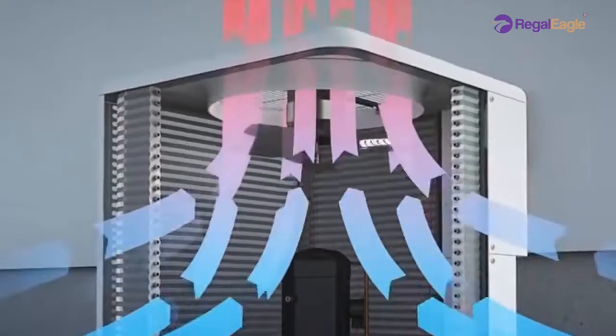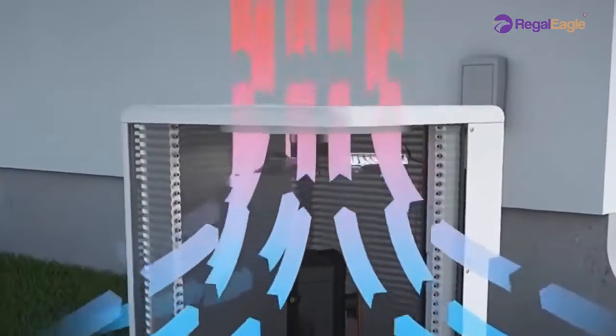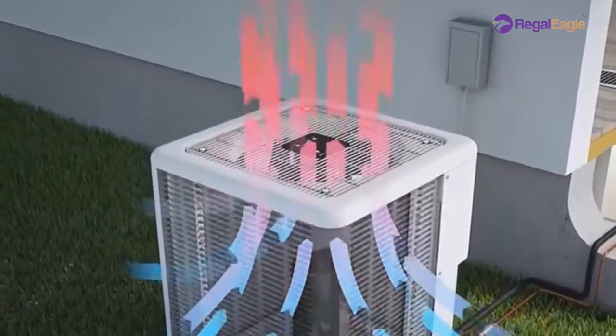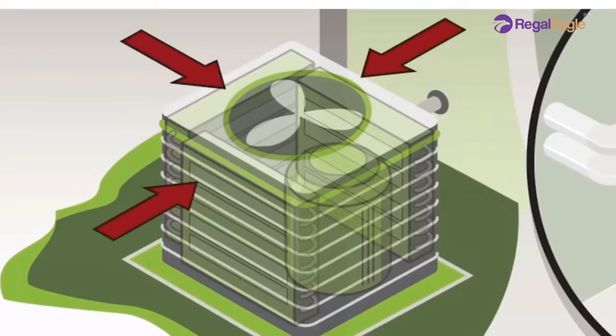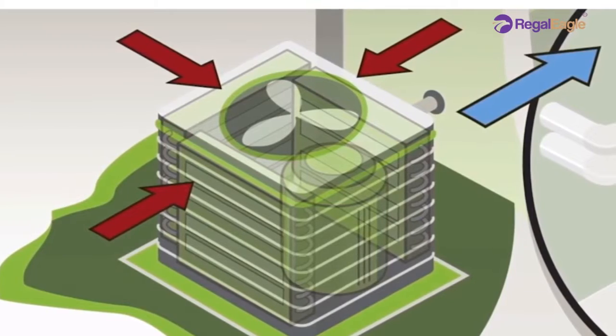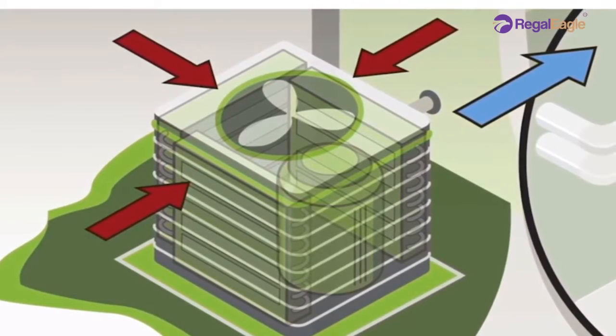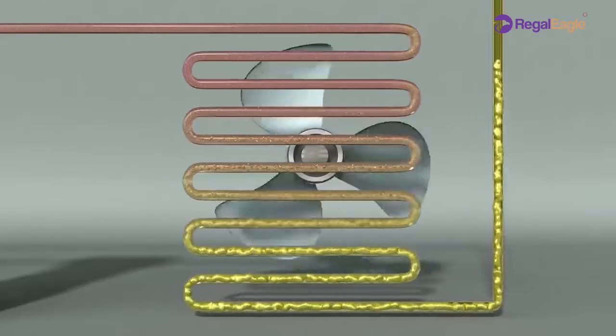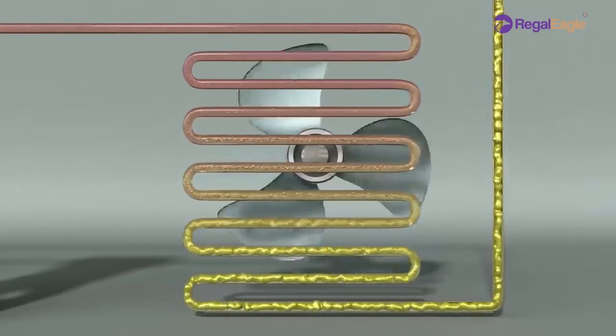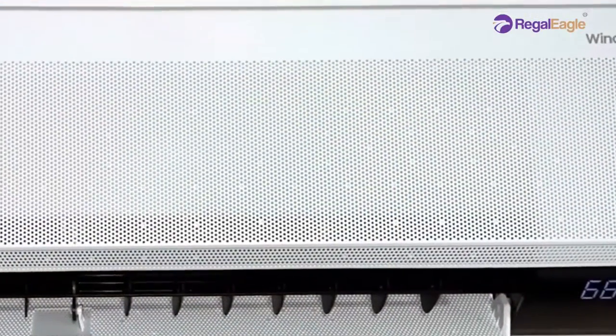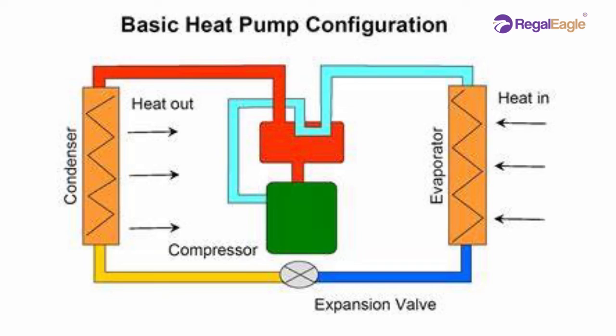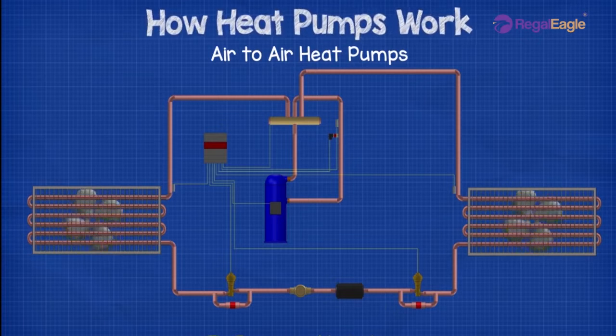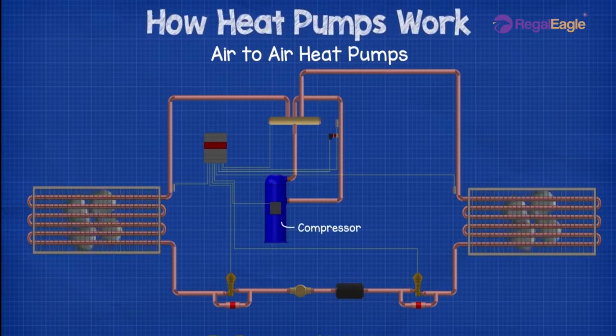With respect to cooling, a HVAC system will usually have an air conditioner or heat pump. An air conditioner only cools, but the heat pump can both heat and cool a home. The refrigerant is key to heat absorption in cooling systems. The refrigerant has high latent heat of vaporization. The refrigerant can take heat from its surroundings to evaporate. Now, let's talk about air-to-air heat pumps. Air-to-air heat pumps are similar to split-unit air conditioners.